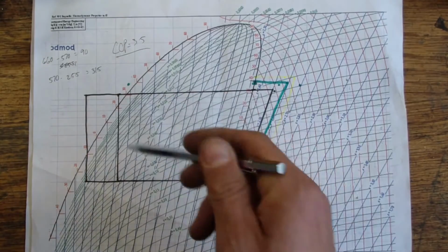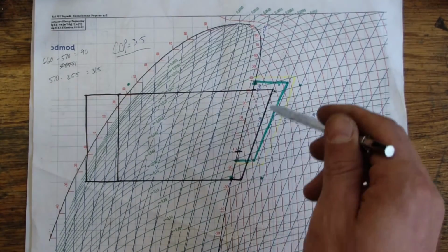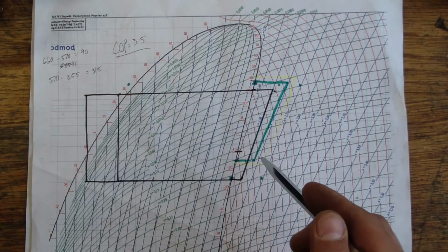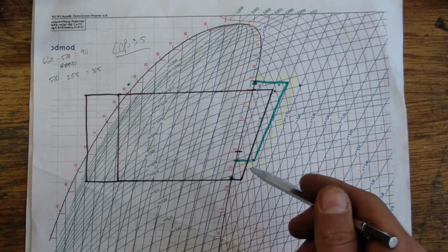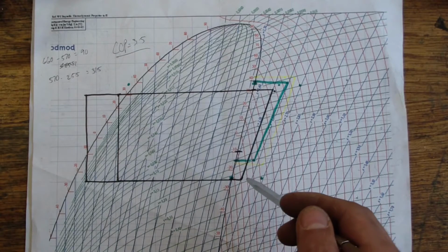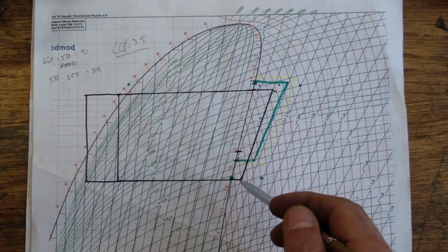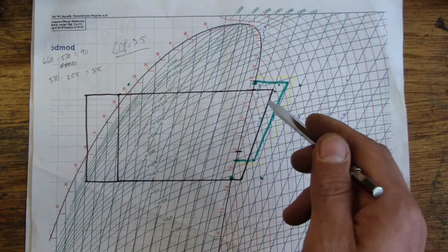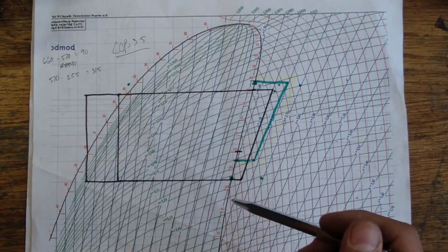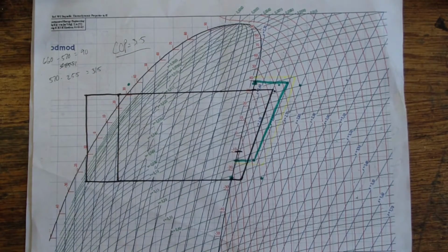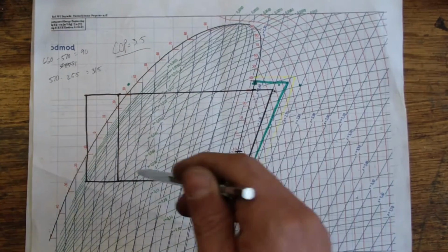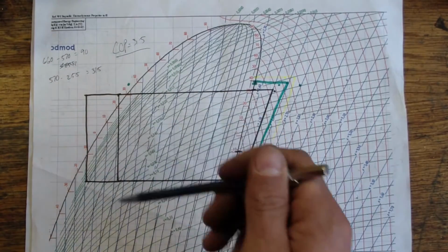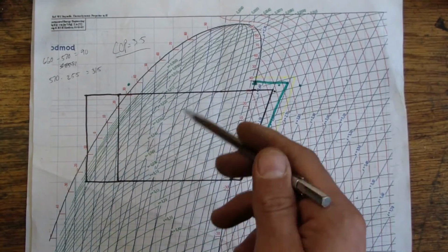We can describe our basic vapor compression cycle with this black line, and the different states that the propane exists in throughout this cycle. So, for instance, we know that there are cases where all the refrigerant is in a vapor state, and that exists within the suction line coming back to the compressor, in the compressor itself, and then the discharge from the compressor, where the gas is superheated and not condensed at all, it's just all superheated gas. Places where we know the refrigerant is liquid, or at least partial liquid, are in the condenser and in the evaporator. The metering device is an interesting place because we can have both a liquid and a gas existing in there, depending on what kind of metering device we're talking about and what part of the throttling that we're discussing.